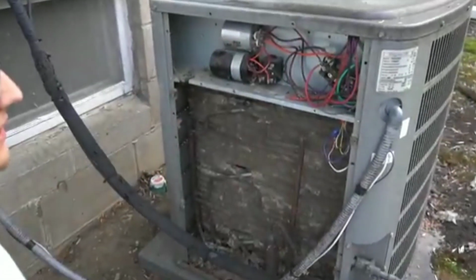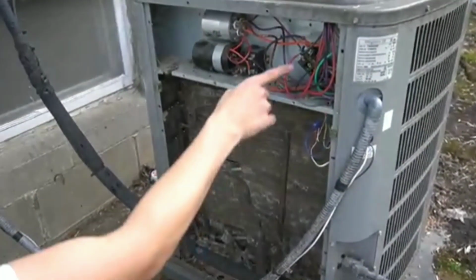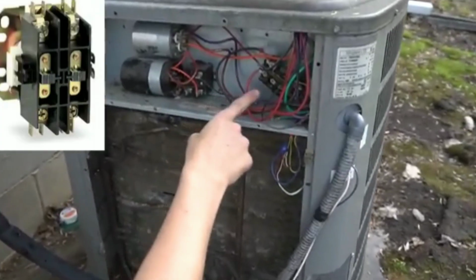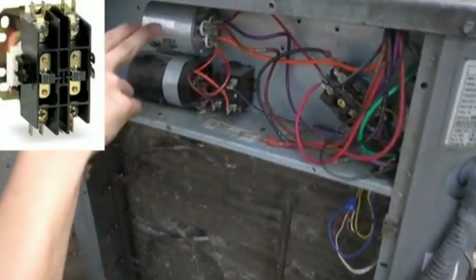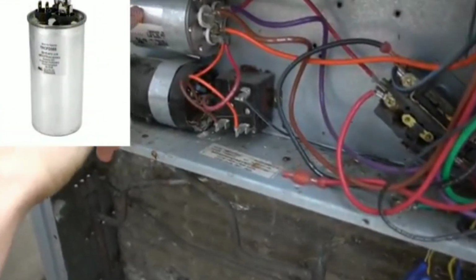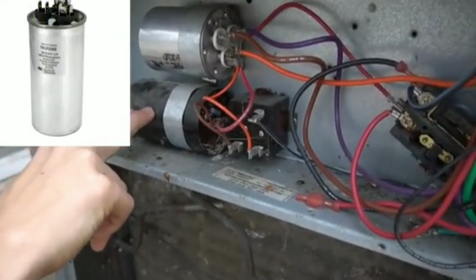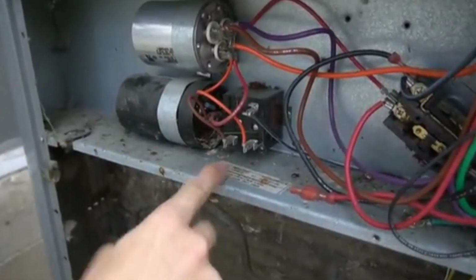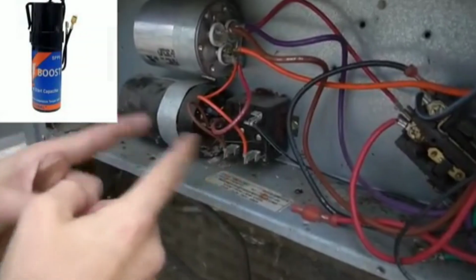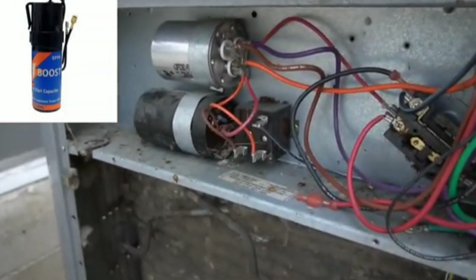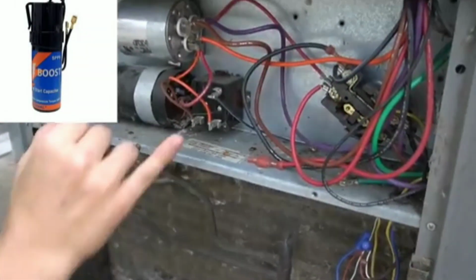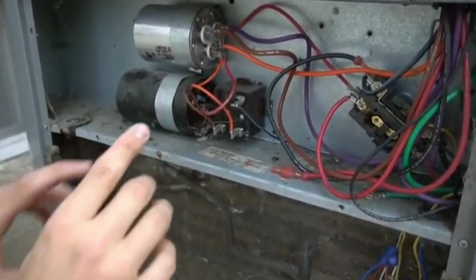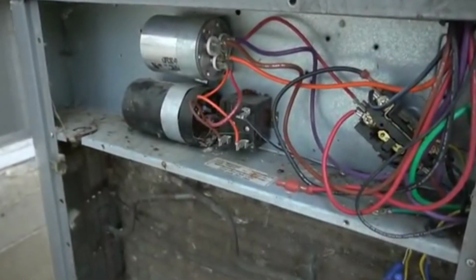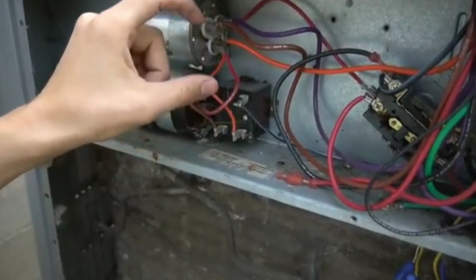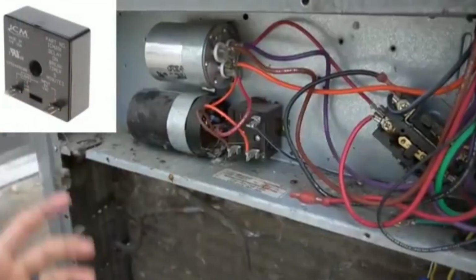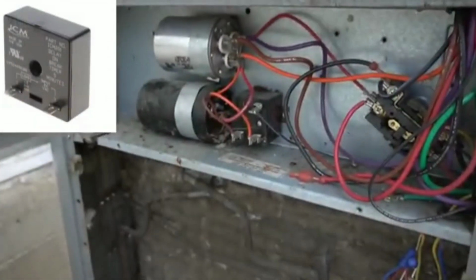And here we have all the electrical components from the unit. This relay right here is called a contactor. This is a run capacitor, a dual run capacitor. This is a start capacitor with a relay. Sometimes it's a hard start kit where both of these are in one. And just so you know, not all air conditioner units will have the start capacitor, and some air conditioners will have other components as well, like a fan delay board or a little control board or some other relays that are installed in this section.